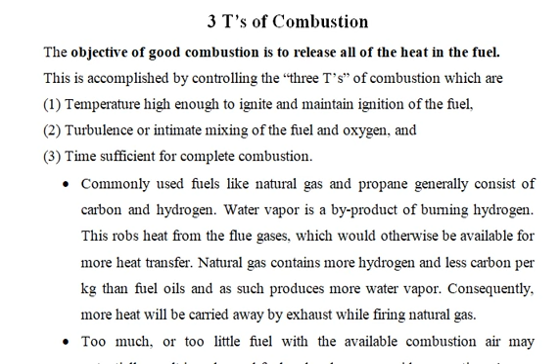Commonly used fuels are natural gas and propane, which generally consist of carbon and hydrogen. Water vapor is the byproduct of the burning of hydrogen. Then we discussed that more heat will be carried away by the exhaust while firing natural gas. Too much or too little fuel with the available combustion air may result in unburned fuel and carbon monoxide generation. If the air is not provided sufficiently, carbon monoxide is generated.